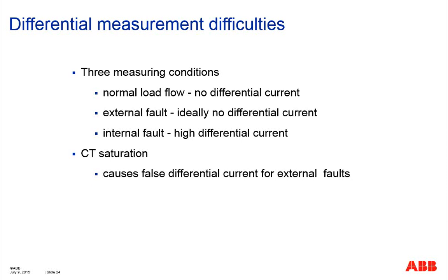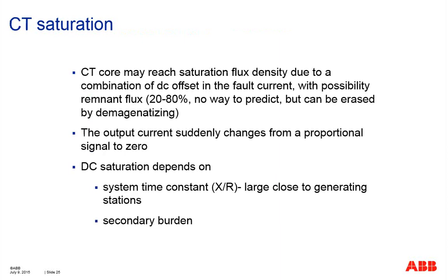So I'm sure this is the common differential philosophy that actually accounts for all types of differential application for lines, for buses, for transformers. They are all the same. So upon CT saturation, you will cause false differential current for external fault. What is CT saturation? The CT core can reach saturation flux density due to a combination of DC offset with the possibility of remnant flux. Okay.